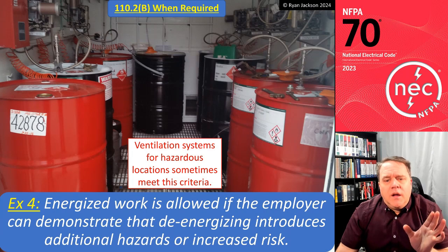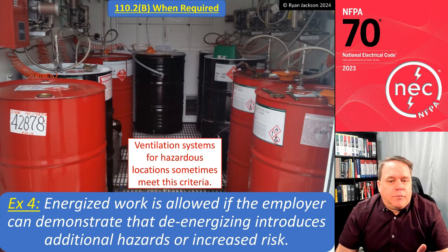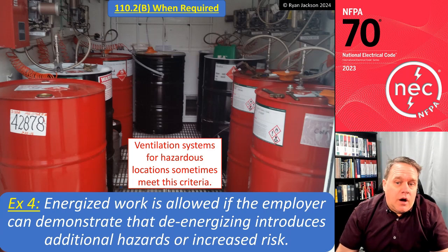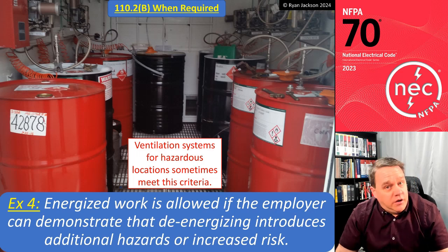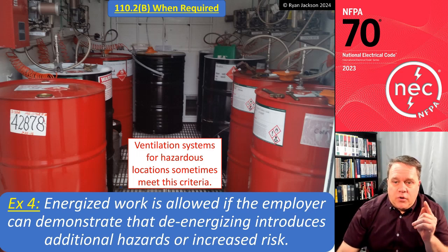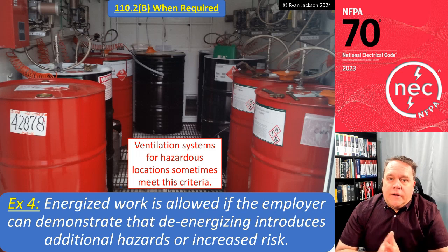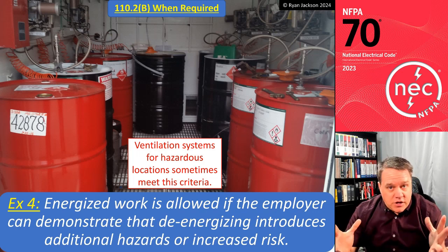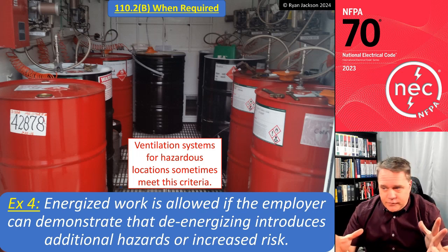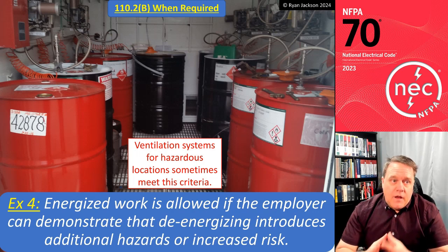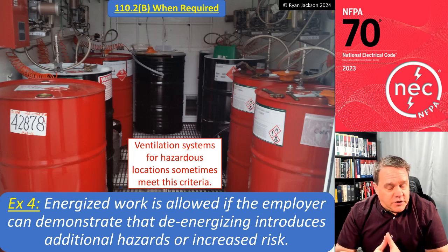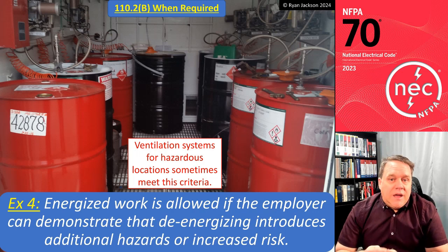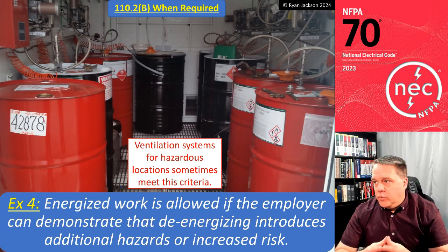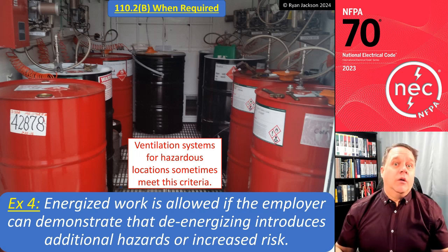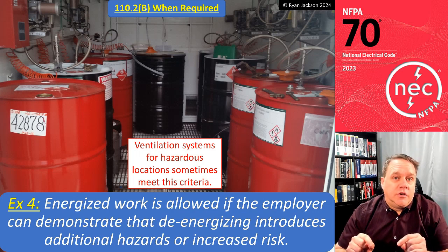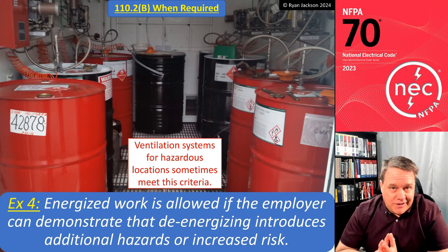Exception 4, energized work is allowed if the employer can demonstrate that shutting it off introduces additional hazards or increased risk. All right, so here in this photograph, we've got a hazardous location, right? We've got all of these barrels of gasoline. You do not want to work energized in this location. Any sort of arc or spark would blow up the room and we'd all be dead. So working on this thing energized in that location would never be allowed.